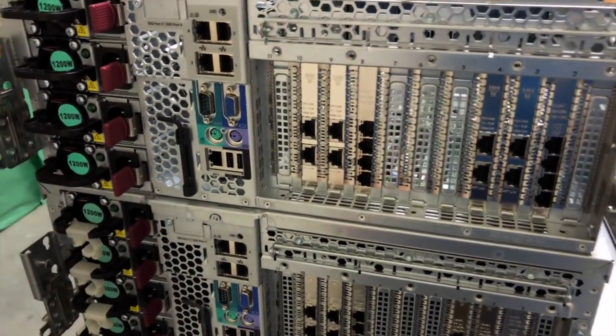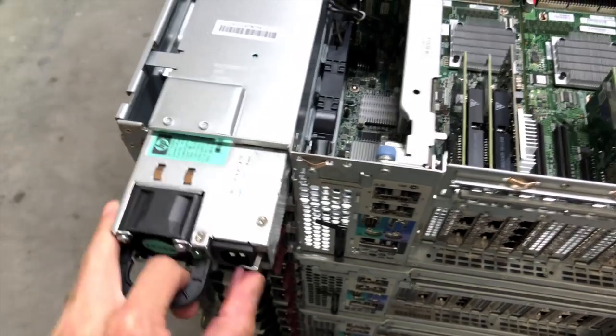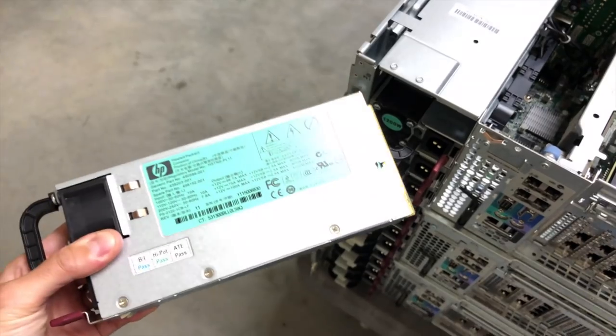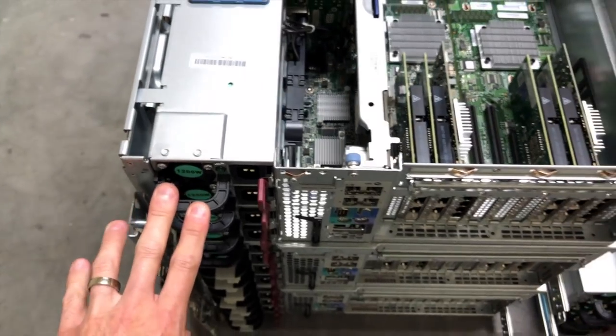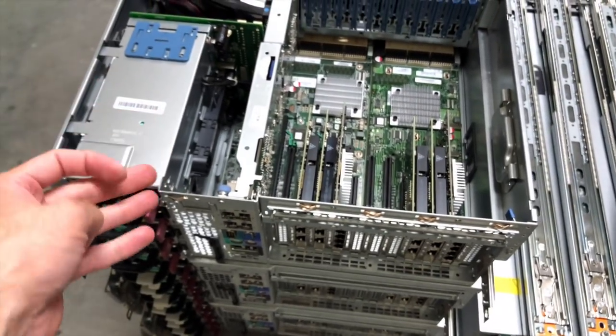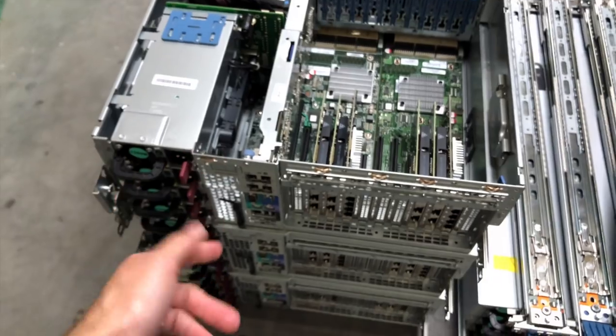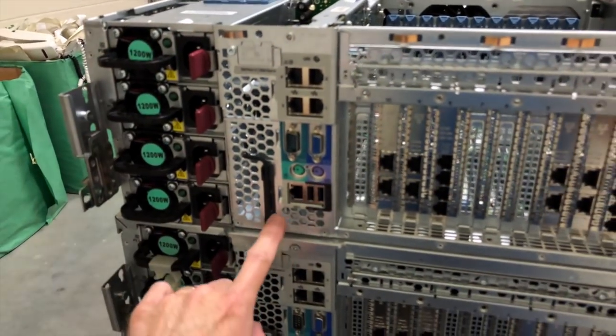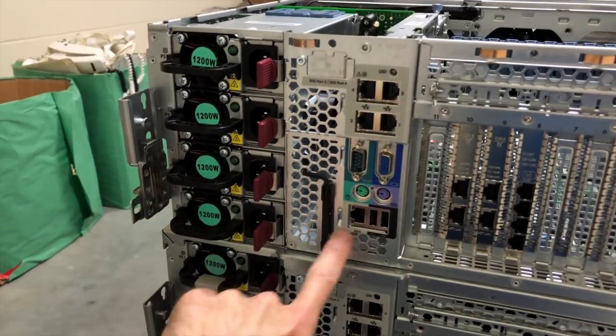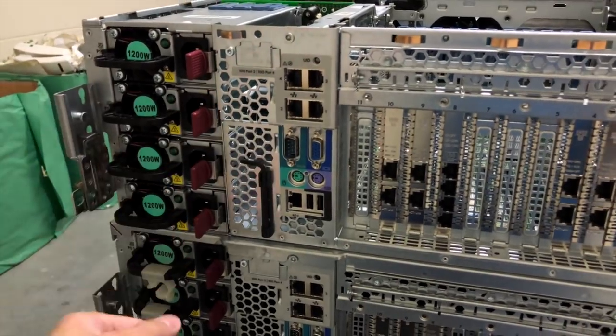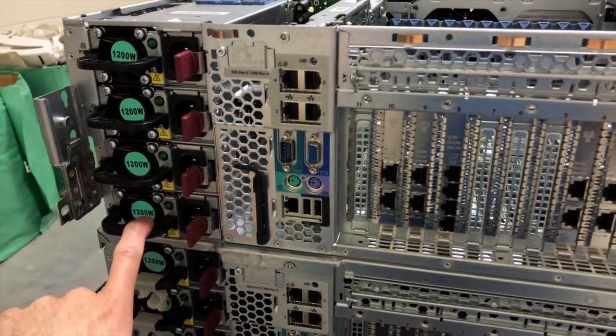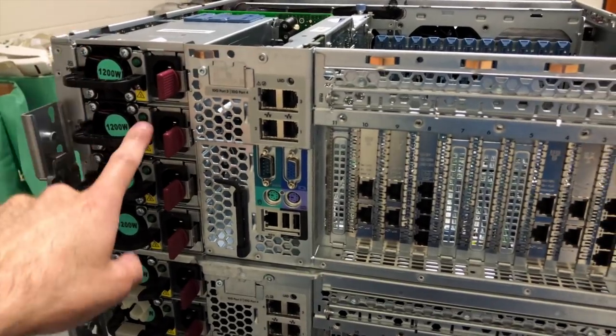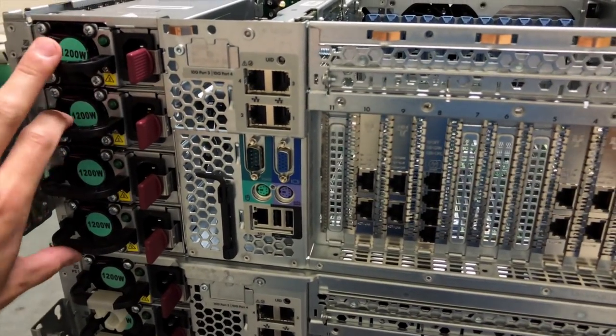Power supply arrangement is a little bit different on this guy in that these are each 1,200 watts. They're physically quite a bit smaller. They do still have a little fan in the back. But this server requires a minimum of two power supplies just to start to kind of wake up. That lights-out management is effectively a computer within the computer. The server doesn't need to be powered on for that lights-out management to work. As soon as the server receives sufficient power, that lights-out management will start to boot up. So, as long as you've got two power cords plugged in the back, lights-out management will wake up, boot up, and then you can get in the web interface to actually remotely press the power button on the front. But because of the way this server is configured with the CPUs and the RAM and everything, you need at least three power supplies to supply enough juice for the server to stay up and running.